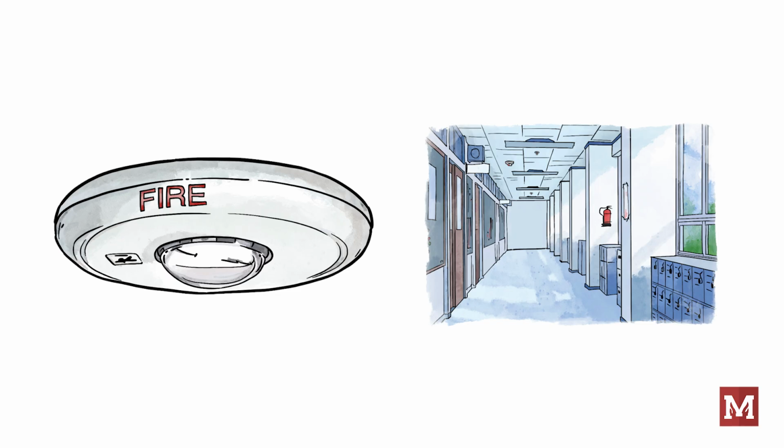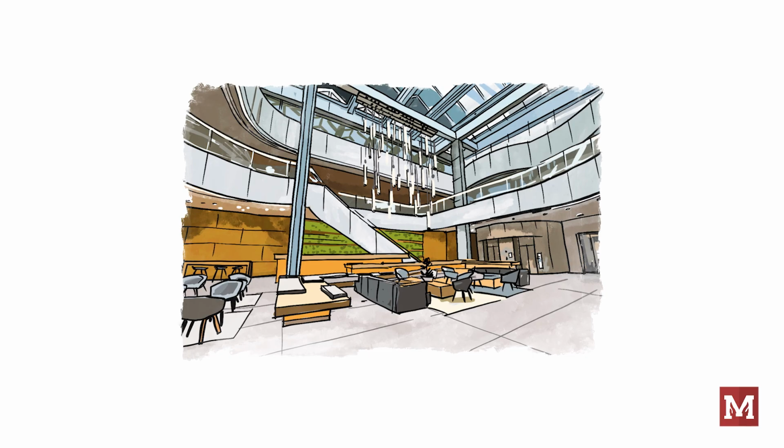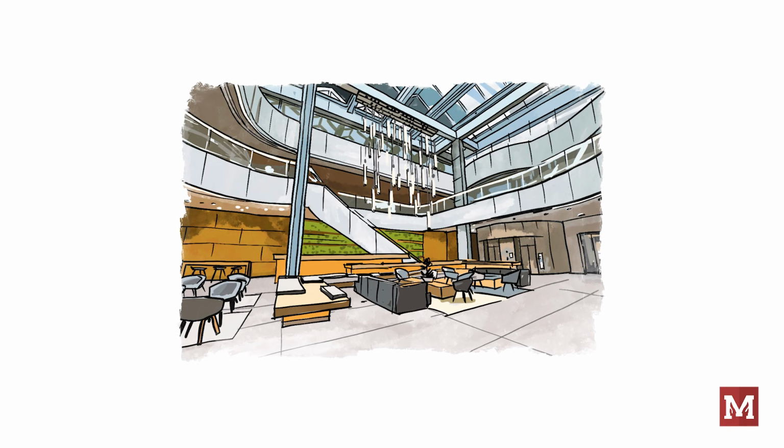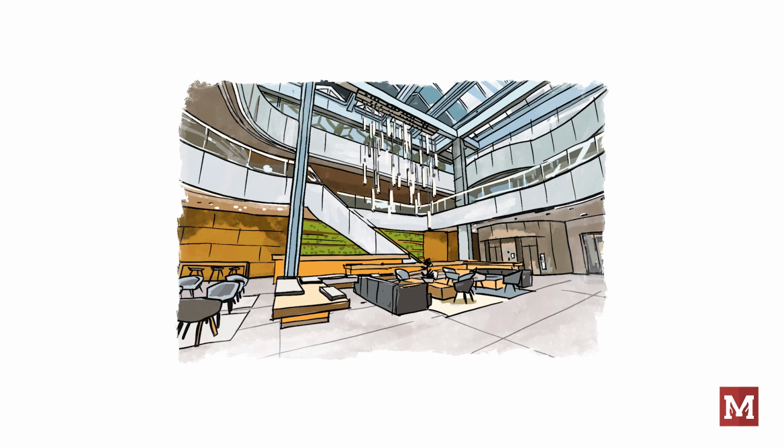Modern fire alarm systems address this by design, and it's really less of an installation issue today. Coverage. In addition to light intensity and synchronization, here's perhaps an ill-defined area that'll take some engineering judgment. Are we allowed to have shadow areas, or part of a space that needs visual coverage but doesn't get it directly from a strobe? Well, yes and no.